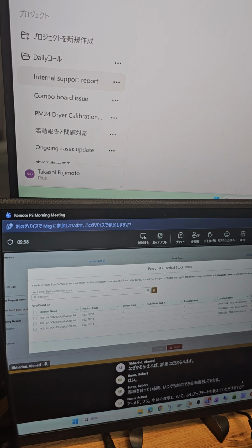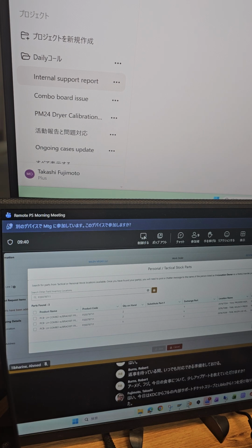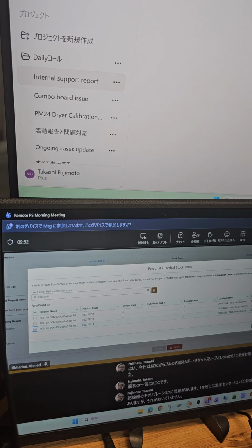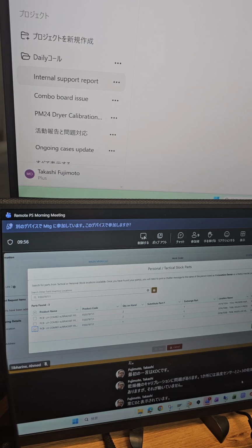First one is KDC. They have a dryer calibration issue. One place had a temperature sensor on dryer 2x3 that is not working, so it showed 0 all the time. I already shared the troubleshooting steps in the feed, so now I wait for their feedback.